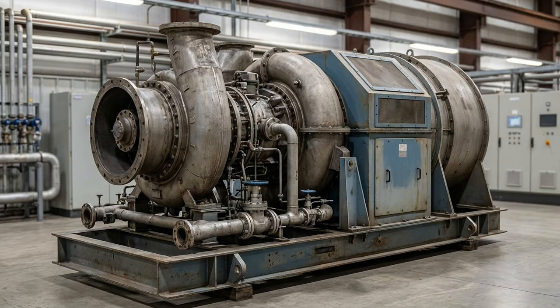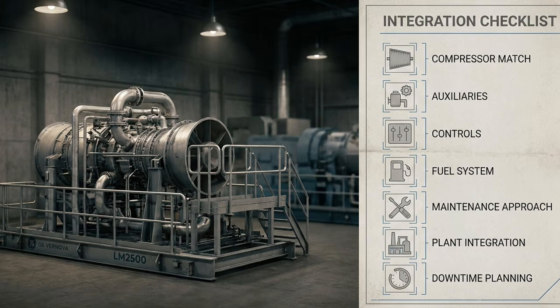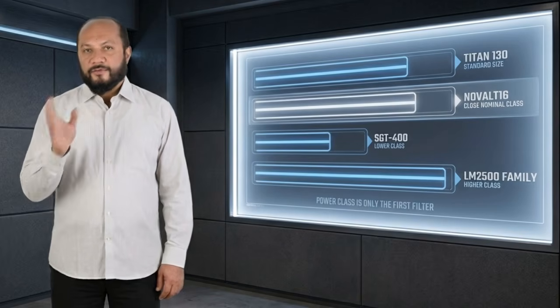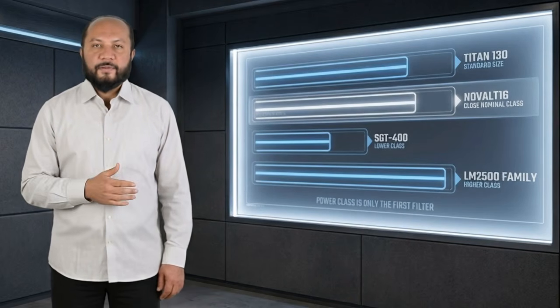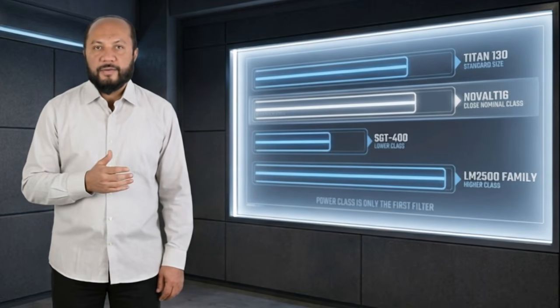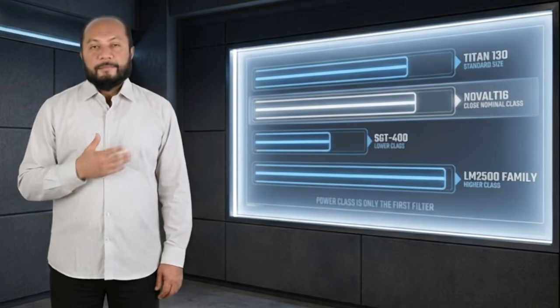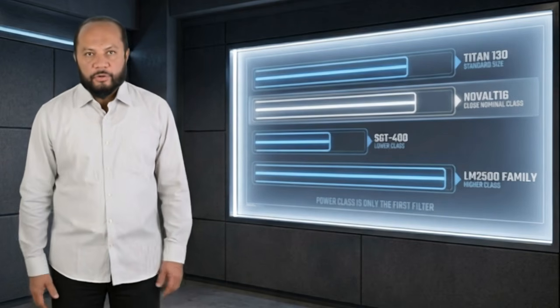The Vernova LM2500 family belongs in the higher power aeroderivative category. Unless a specific LM2500 variant is identified, it is better to describe it by family and application class, rather than assigning one simplified output number. An LM2500 family solution brings a different design and maintenance philosophy. It may offer higher capacity, but it also changes the package, driven compressor match, auxiliaries, maintenance approach, controls, and plant integration requirements. At the first screening level, Nova LT16 is close to the Titan 130 nominal power class. SGT400 is lower and LM2500 family equipment is higher. But power class is only the first filter. It is not the engineering conclusion.